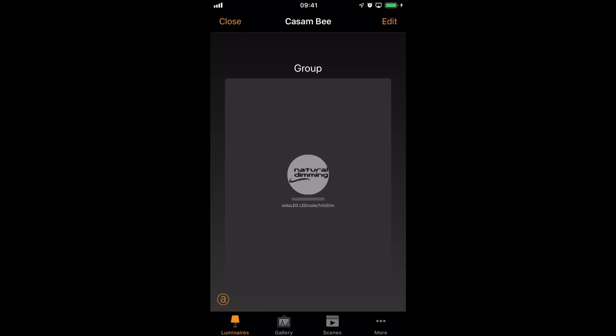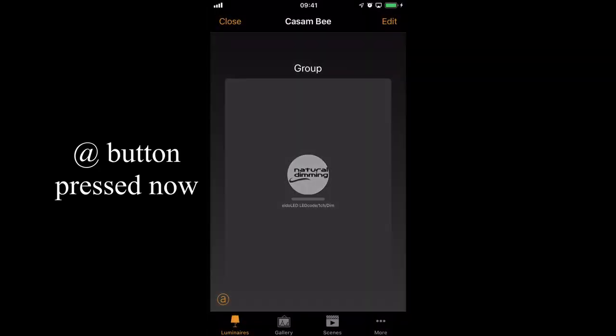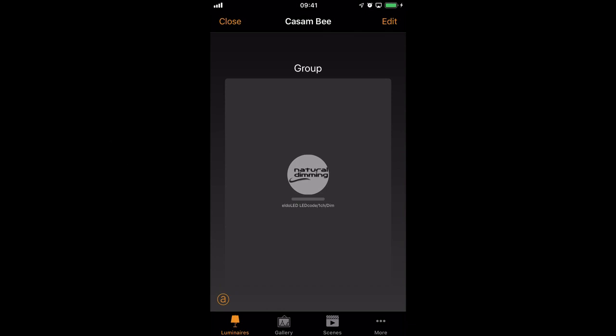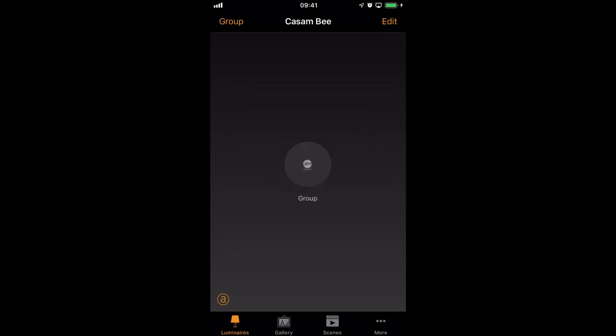As you can see, I've opened the group. The A button is still visible in the bottom left hand corner. But because I have the group open, and I press A, it will only resume automation for the luminaires in that particular group. If I had any more luminaires in my network, it would not affect any of those, so they would remain under manual control.